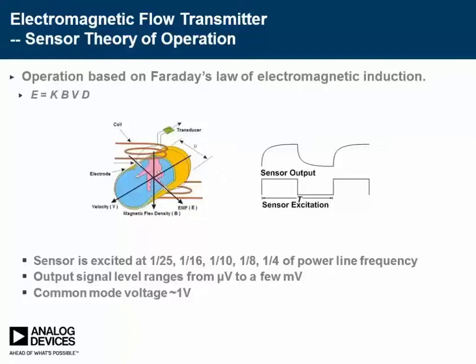Mathematically, we can state Faraday's law as E = K × B × L × V, where V is the velocity of the conductive fluid, B is the magnetic field strength, L is the spacing between the pickup electrodes, E is the voltage measured across the electrodes, and K is a constant. Since B, L, and K are either fixed or can be calibrated, the equation reduces to E being proportional to V. Most electromagnetic flow meters use a low-frequency DC rectangle waveform to excite the sensor coil.